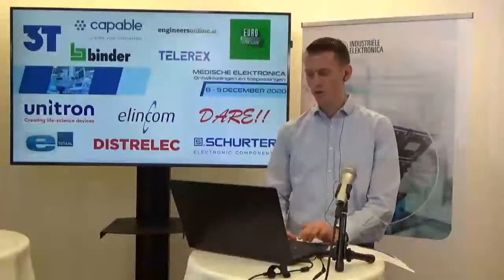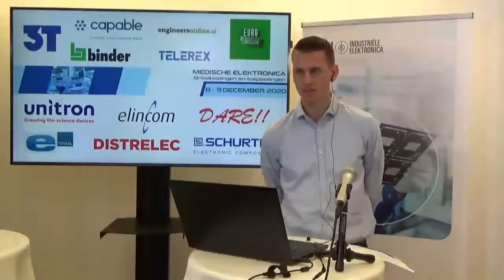Is the IEC 60601 important for the new MDR regulation? Yes, it is important. This is part of this regulation. I think in Article 12, they speak about the protection of the patient and operator. So if you have a new design with your medical equipment, at the end you need your qualification, and you have to go to a notified body to get your certification to bring the product on the market, and you have to be under the norm of the IEC 60601 to protect the patient and the operator. So yes, it is very important.